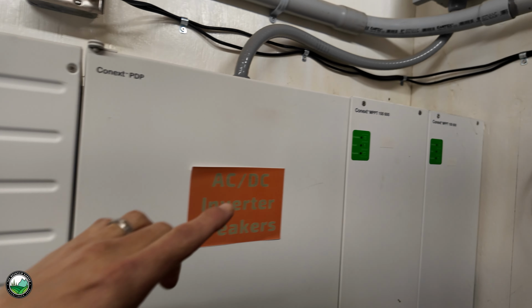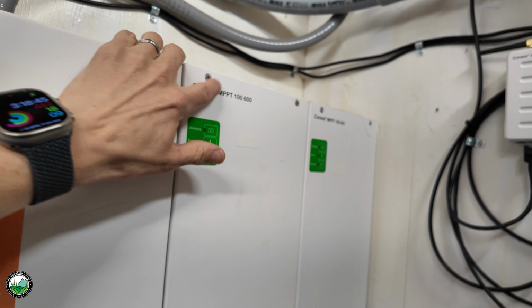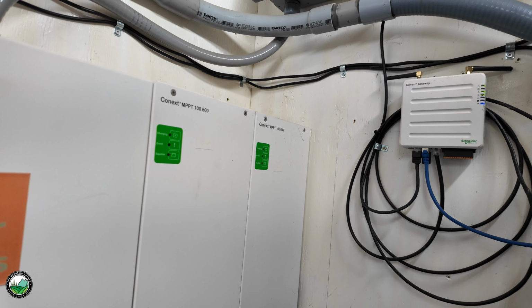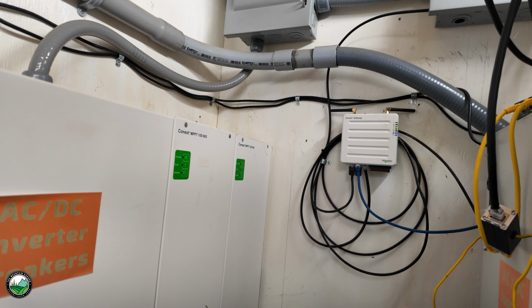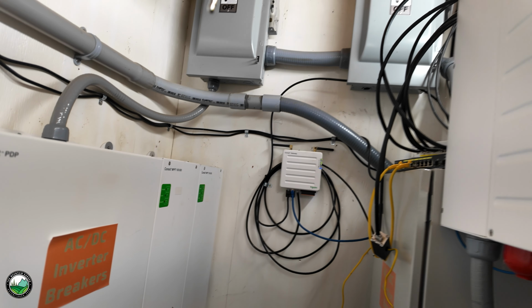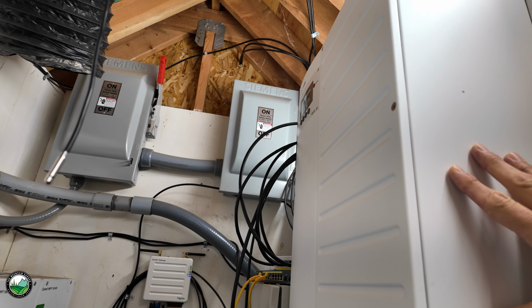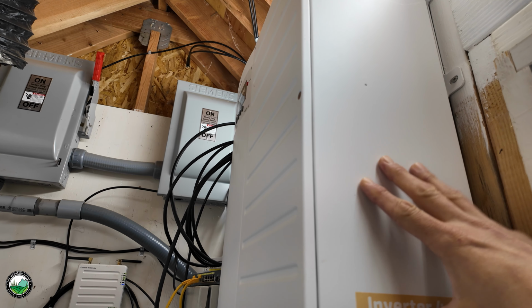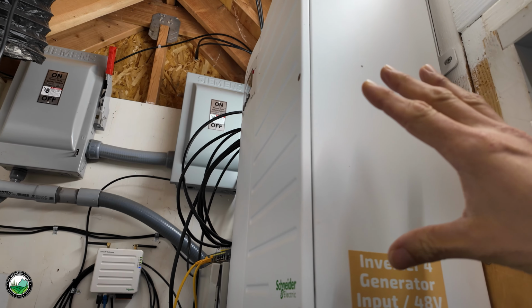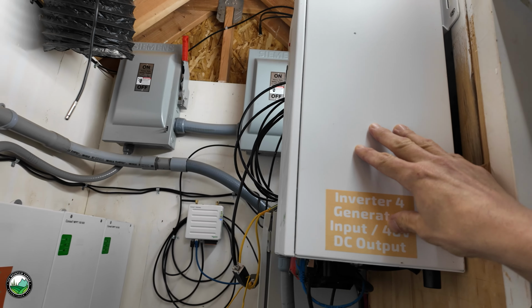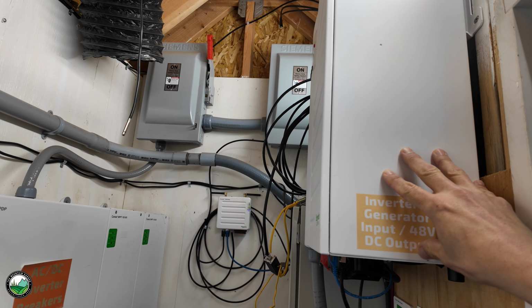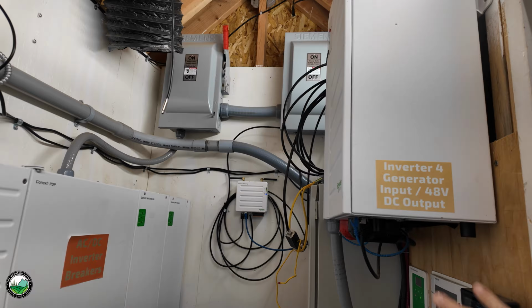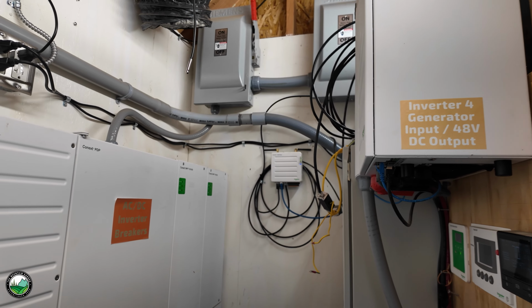We have the 100 amp DC charge controllers, 2 of them, one on each solar array. We have the Schneider internet connected gateway, and then this spare inverter and charger we use to connect to the diesel generator. It was at the time one of the cheapest ways to get a high output 48 volt charger. We have some other monitoring equipment and disconnect stuff here as well.